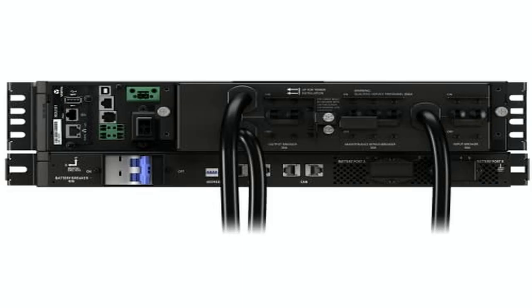Lithium-ion cells don't need the regular watering, equalization cycles, or temperature-controlled rooms that a traditional UPS demands. Over a 5-year horizon, you'll see fewer maintenance calls, lower electricity usage because the charger operates at higher efficiency, and no need to buy replacement batteries every 2 to 3 years. For a small IT department that's already stretched thin, those hidden savings can be the difference between a justified capital expense and a lingering budget hole.